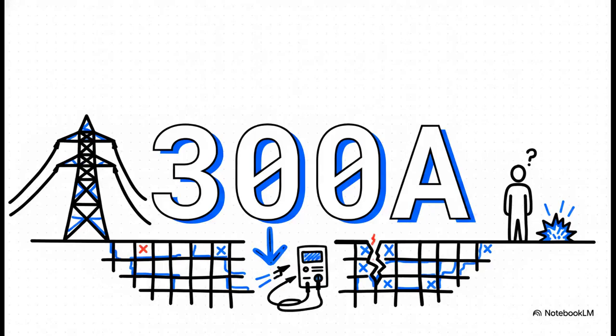And they don't just blindly trust the math either. To make sure these existing circuits are safe, engineers perform staged fault and integrity tests. They'll typically pump 300 amps of test current directly through the ground grid infrastructure. By doing this, they can hunt for high-impedance paths, weak ties, or broken underground copper wires. It's literally about finding the broken wire with test equipment before it finds a human being during a real fault.